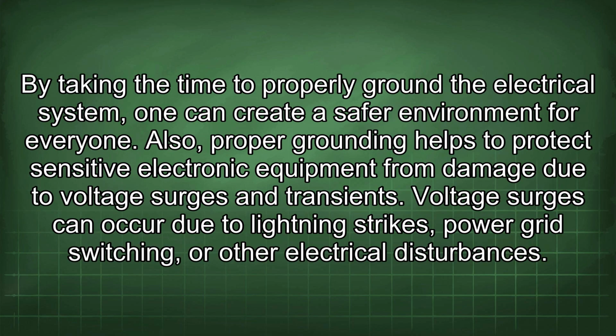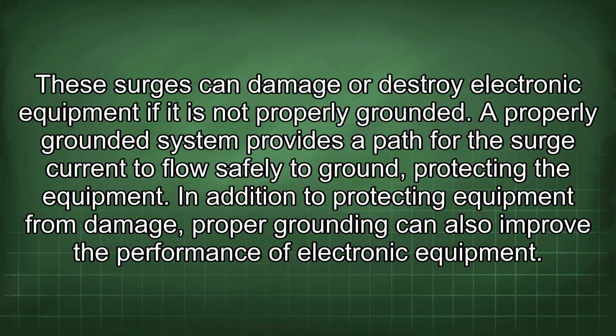By taking the time to properly ground the electrical system, one can create a safer environment for everyone. Also, proper grounding helps to protect sensitive electronic equipment from damage due to voltage surges and transients. Voltage surges can occur due to lightning strikes, power grid switching, or other electrical disturbances. These surges can damage or destroy electronic equipment if it is not properly grounded. A properly grounded system provides a path for the surge current to flow safely to ground, protecting the equipment.